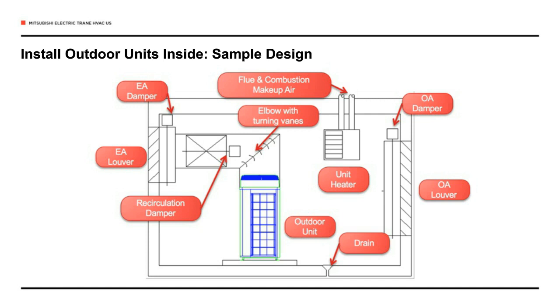This is essentially, you've got one spot now instead of putting duct coils or baseboard radiation all over the building, which can get costly if it's not already there as part of the infrastructure. It's one central location to put that equipment. We're seeing this less and less because it's fairly expensive. You can imagine all those dampers and louvers and operators and the controls required to operate that. We're seeing this less and less and seeing more of the flash injection take the place of this design.